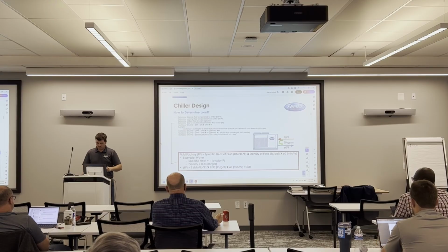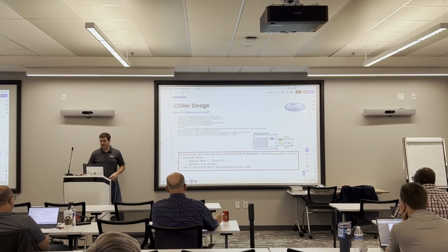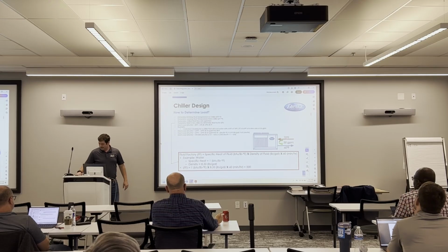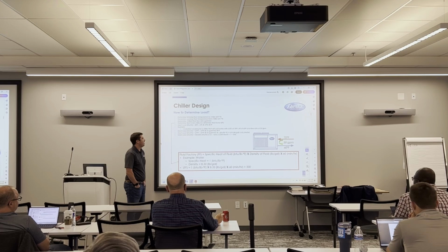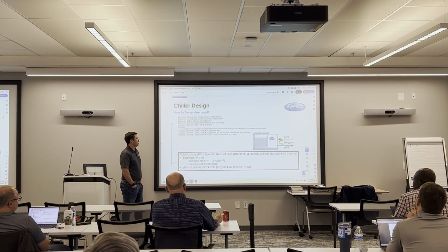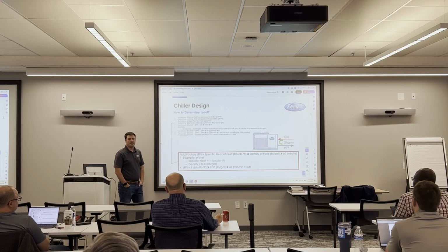Alrighty. So that's one way to quantify heat load. I wish it was always that easy, but it's not. Sometimes customers will call in and say, hey, I have a 100-gallon tank I'm trying to drop from 100 degrees to, say, 90 degrees in an hour. Is that enough information to size a chiller?